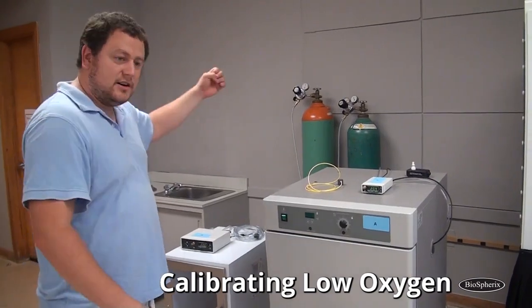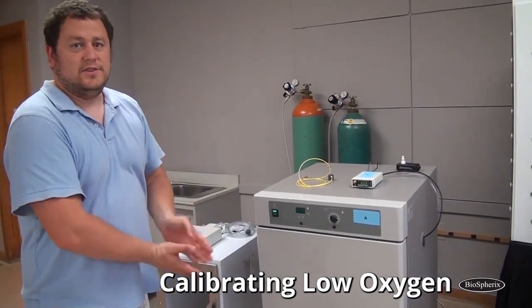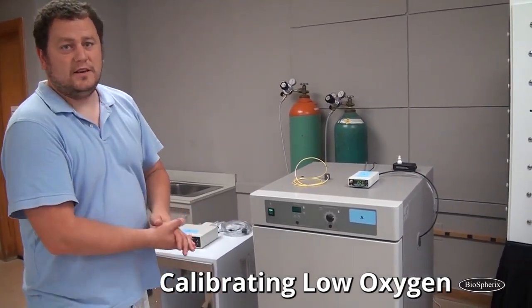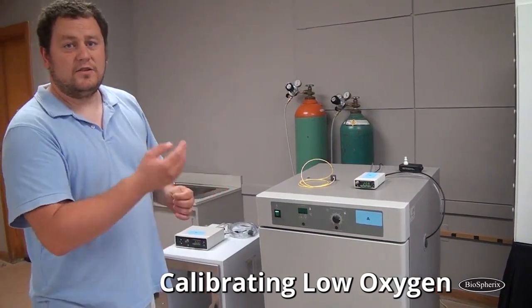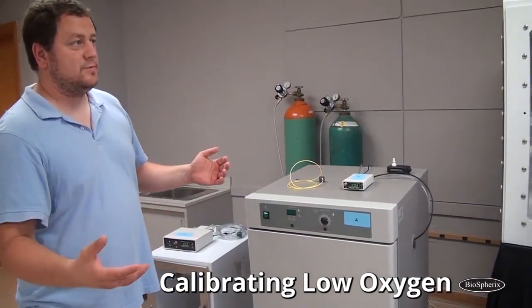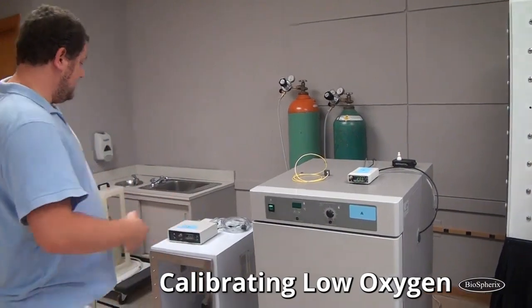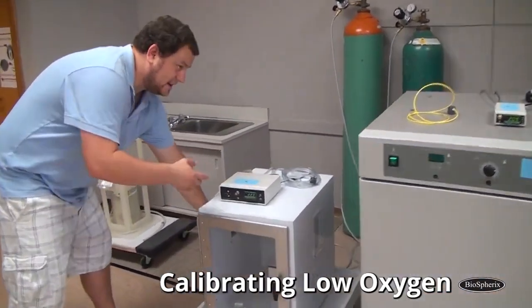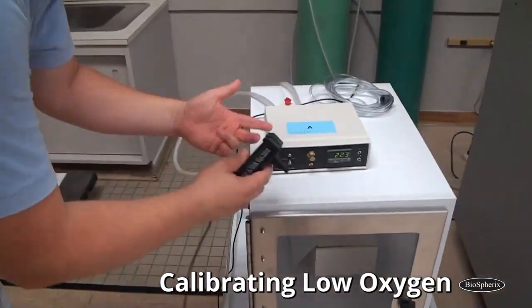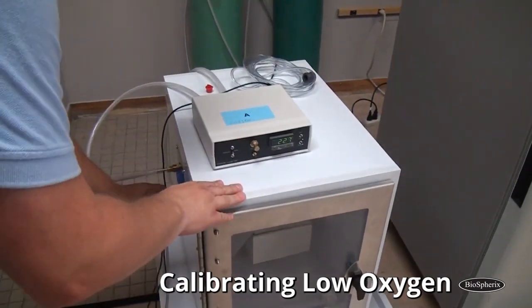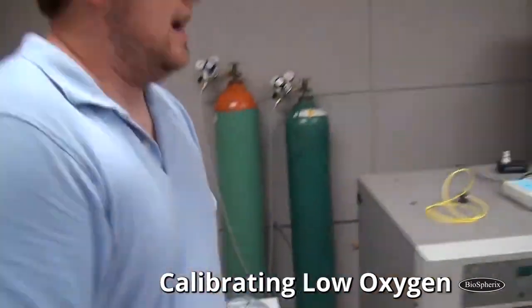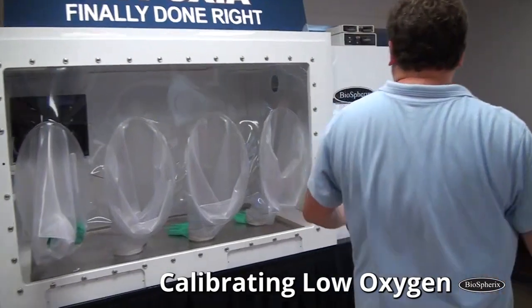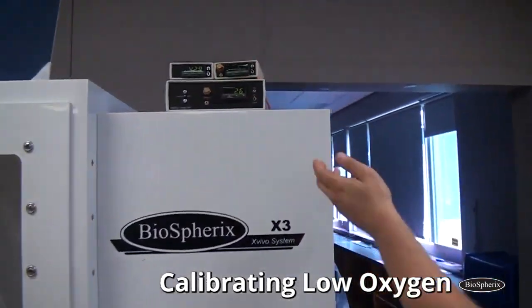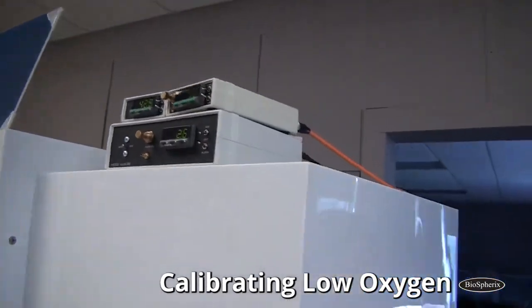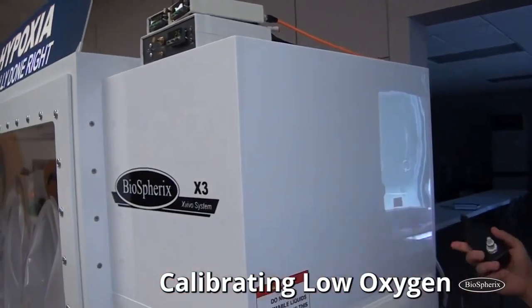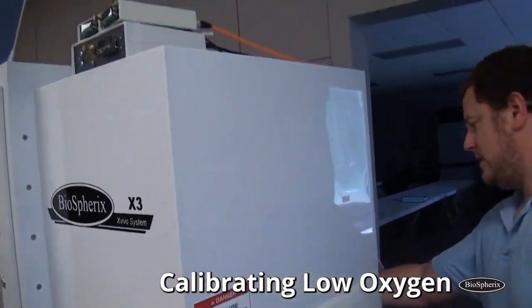You take the sensor from the adapter plate, you do the 0, make your adjustments if you need to, then you do your span to room, make the adjustments if you need to. As you can see, it's actually a little easier on these because your sensor is pretty close to where it needs to be. Same with on the glove boxes. You're just going to run your calibration tubing here, and you've got your sensor right here. You're already in the close area.